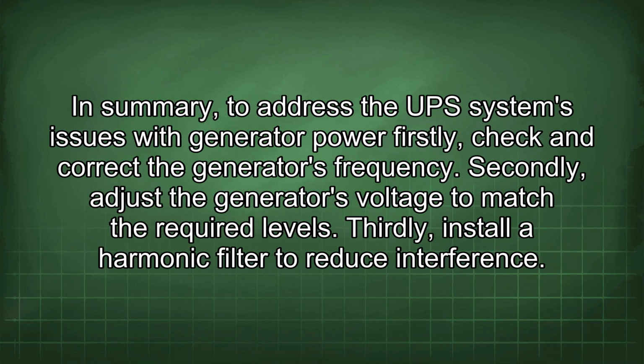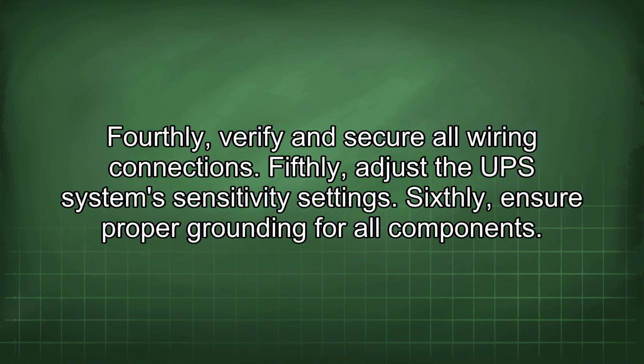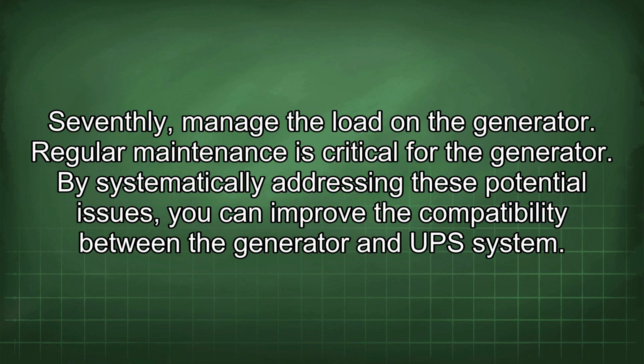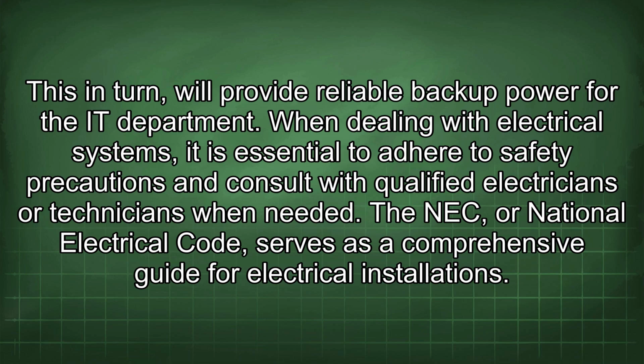In summary, to address the UPS system's issues with generator power, firstly, check and correct the generator's frequency. Secondly, adjust the generator's voltage to match the required levels. Thirdly, install a harmonic filter to reduce interference. Fourthly, verify and secure all wiring connections. Fifthly, adjust the UPS system sensitivity settings. Sixthly, ensure proper grounding for all components. Seventhly, manage the load on the generator. Regular maintenance is critical for the generator. By systematically addressing these potential issues, you can improve the compatibility between the generator and UPS system. This in turn will provide reliable backup power for the IT department.